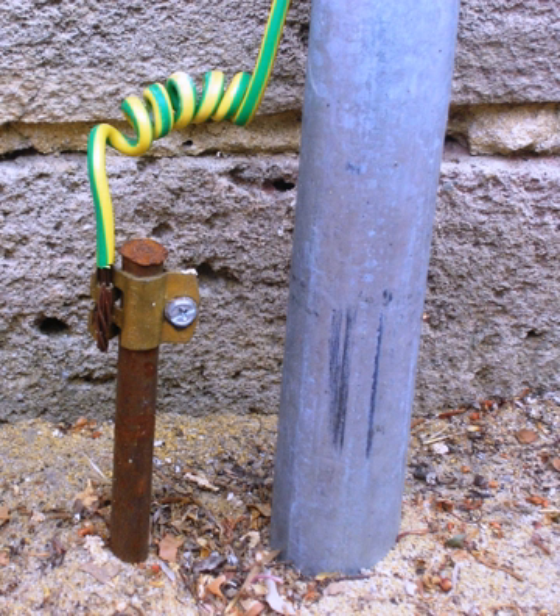See Kirchhoff's circuit laws. By bonding, interconnecting, all exposed non-current carrying metal objects together and to other metallic objects such as pipes or structural steel, they should remain near the same voltage potential, thus reducing the chance of a shock. This is especially important in bathrooms where one may be in contact with several different metallic systems such as supply and drain pipes and appliance frames.